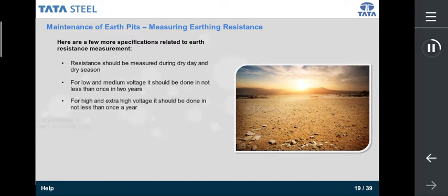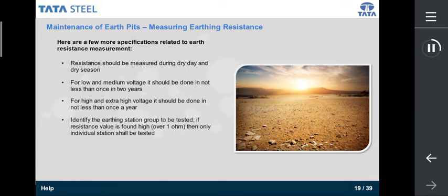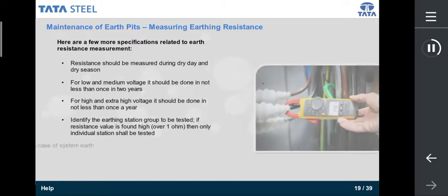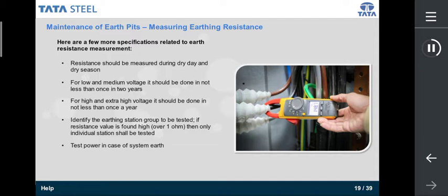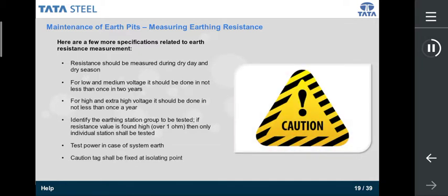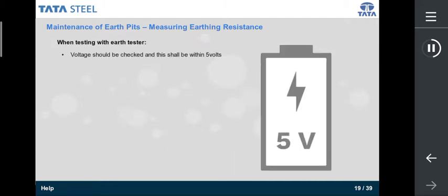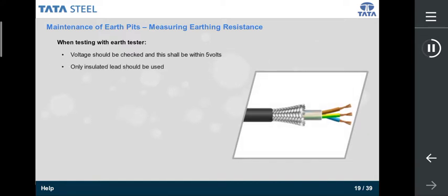Identify the earthing station group to be tested. If the resistance value is found high, that is over 1 ohm, then only individual stations shall be tested. Test power in case of system earth. Caution tag shall be fixed at the isolating point. Voltage shall be checked and this shall be within 5 volts. Only insulated lead should be used. The lead should be as short as possible.